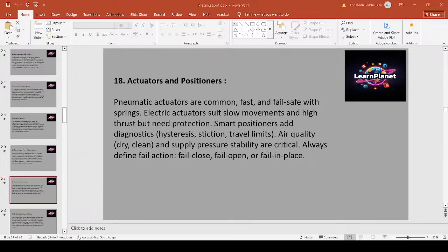Pneumatic actuators are preferred for speed and fail-safe spring action. Electric actuators give precise control and high thrust but require electrical protection and sometimes gearbox maintenance. Smart electropneumatic positioners provide diagnostics like travel time, hysteresis, and valve signature. Integrate these into CMMS for condition-based maintenance. Ensure instrument air quality, dry and oil free, and stable supply pressure for repeatable performance. Define and test fail action, fail open, close, or in place, and ensure the logic enforces it under loss of power scenarios. Example: fit a smart positioner on a globe valve on a feed controller to track friction and trigger maintenance when travel time degrades.